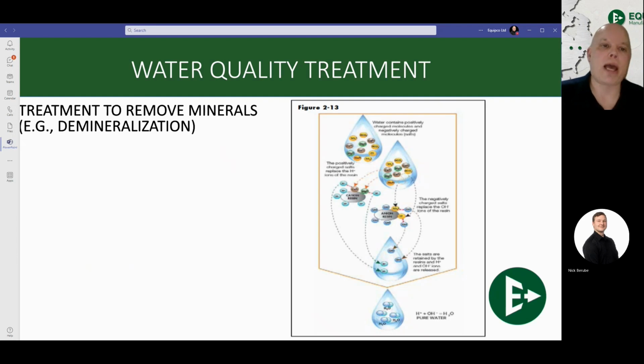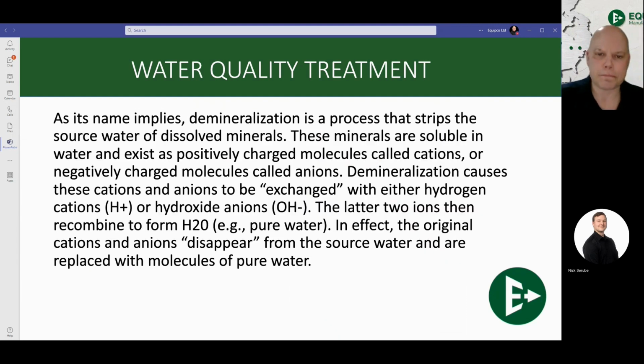The best solution is to actually use demineralized water, where we've taken those sodium ions, your magnesium ions, your lime, and so on, and replaced them through ion exchange in the demineralization process, leaving strictly dihydrogen monoxide, or H2O, straight pure water. Demineralized water is extremely good for a hydronic system. You don't have any scale to build up, and it gives extremely long life. That's going to be a much better solution for you long-term down the road.